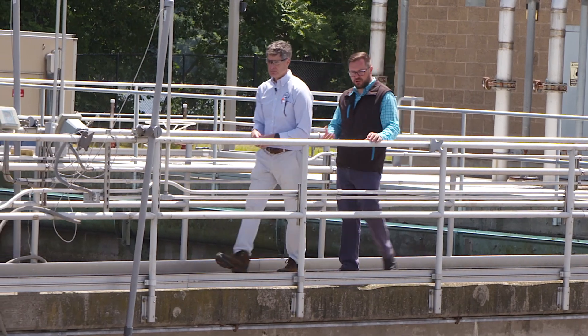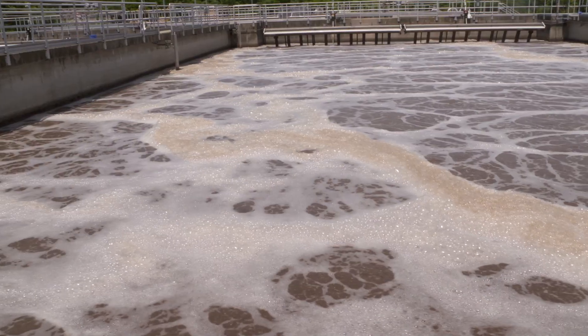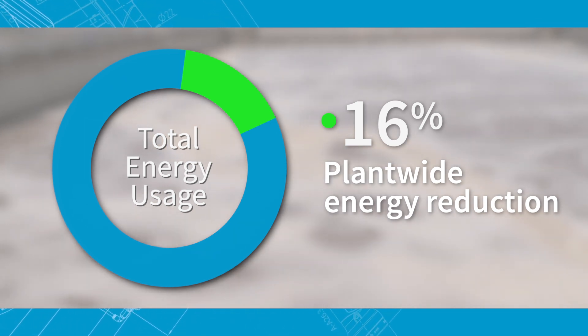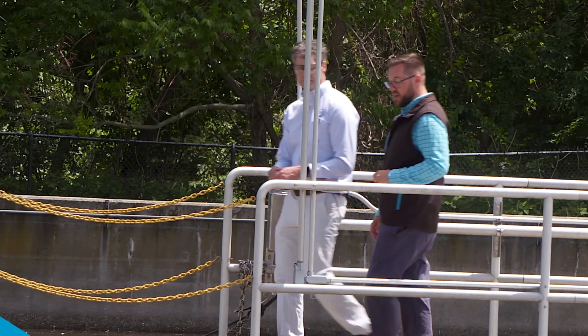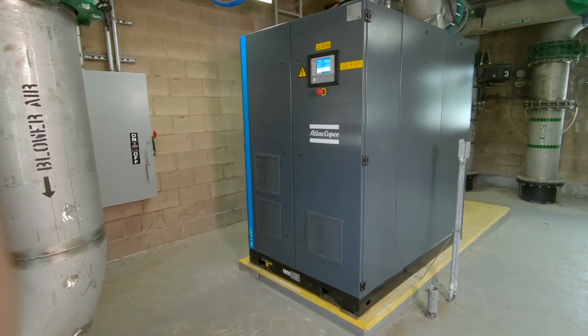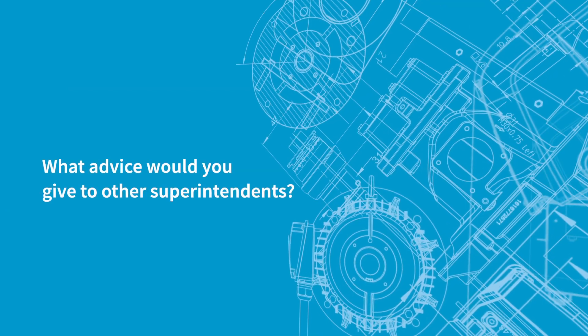You were reviewing your energy bills before the new ZB VSD Plus turbo blowers went in and after. What was it that you saw? We set a record for May — as compared to last year we were 16 percent lighter in energy demand, and that's kilowatt hours. Most of that energy savings is related to aeration. So we're going to buy our third unit this capital improvement year and can't wait to put it in and do the energy calculations, the efficiencies, and brag about them. I would venture to say that about 50 percent of all plants are working on blowers that are not what they should be.